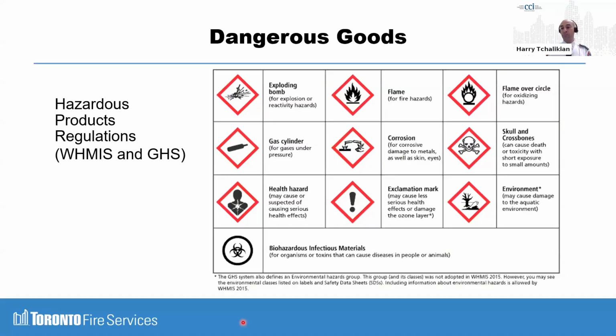So there's not much else to do except put it in your fire safety plan and address the fire safety planning requirements. But other things like if you're storing pool chemicals, please address now it's in 3.1.2, the bare minimum, and then in 3.2.7 for further expansion in terms of if you don't meet the small quantity exemption. Definitely make note of any hazardous materials, anything that meets the definition of dangerous goods. You now have to explicitly address it. And we could have enforced this already, but it may have been an oversight previously.